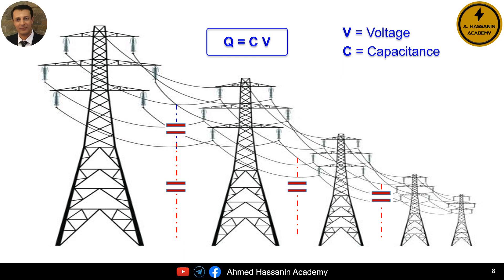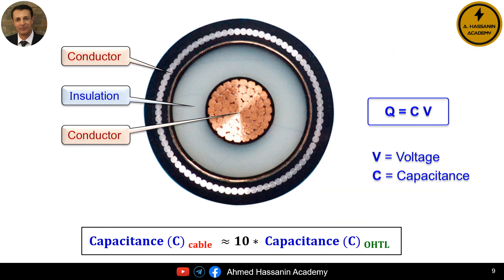Are the self-capacitances present only in overhead lines? Certainly not, because underground cables are also used for electrical power transmission. The cable also acts as a capacitor and therefore the cable can store electric charge in the insulating medium. Also, Q equals C times V. However, the value of capacitance C also depends on the type of insulating material. This means that if the insulating material is air, the value of capacitance will be different than if the insulating material is XLPE, as in the case of underground cables. Therefore, the value of capacitance C in cables is about 10 times greater than the value of capacitance C in overhead lines.